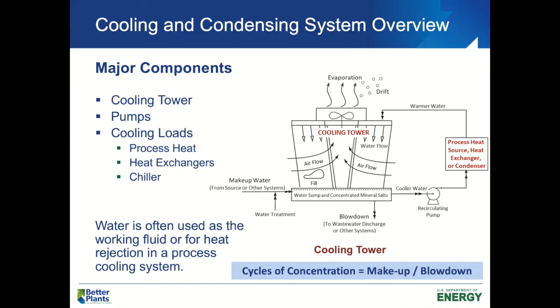Another key metric to note while talking about cooling towers is the cycles of concentration, which is the ratio of the makeup volume divided by the blowdown volume. It gives us an indication of the performance of the cooling tower, right? Pretty much it is how many times you're recycling, recirculating the water before essentially throwing it out. So the higher the number, the better, and five to six cycles of concentration is something that is achievable on a cooling tower.